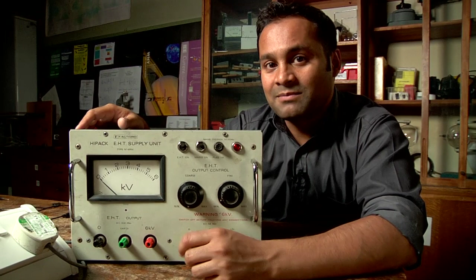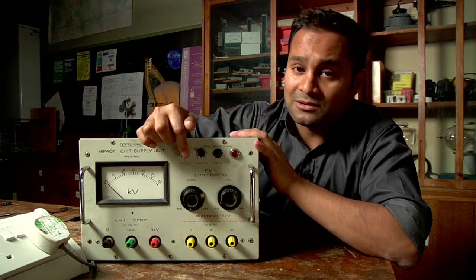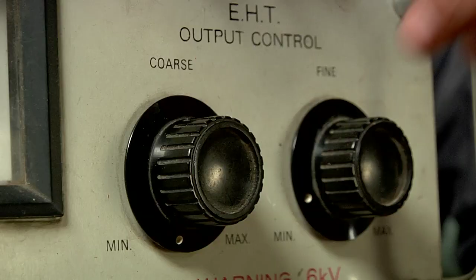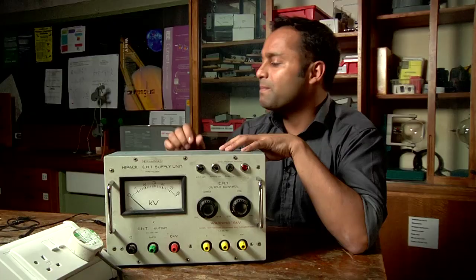Now the reason why it's safe is that there's a high value resistor in series with the high voltage supply here, so the maximum current you can get out of it is not really big enough to do you any harm. Now before doing anything else, I make sure that all the switches are set to off and the voltage controls are set to 0.